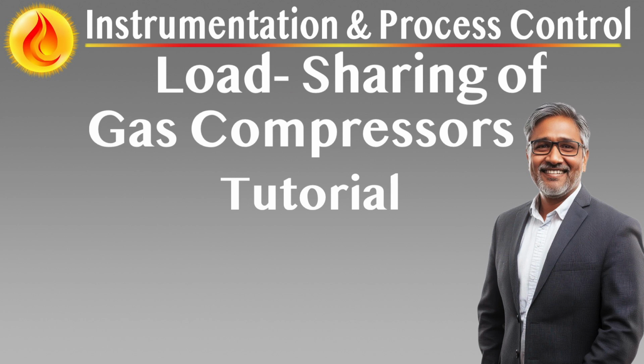Operational benefits. Throughput optimization maintains target production rates without unnecessary recycling or blow-off. Energy efficiency uses performance actuators before resorting to recycle-based throttling, minimizing losses. Surge safety ensures that surge protection mechanisms are always prioritized under restrictive flow conditions. Responsiveness, capable of handling both gradual load changes and sudden disturbances with tailored control actions.